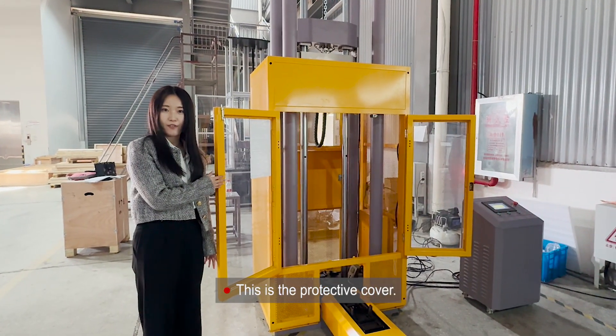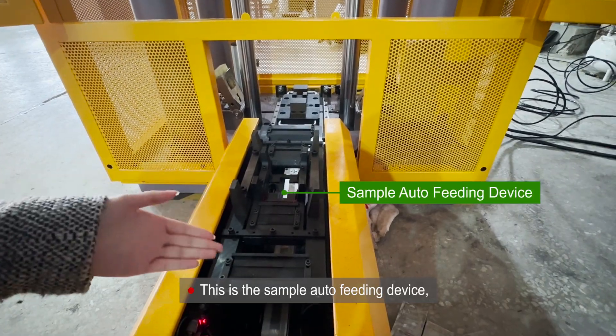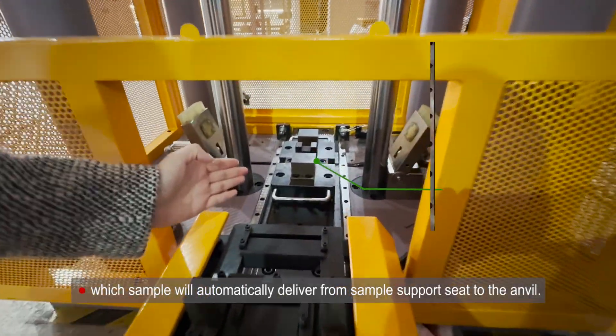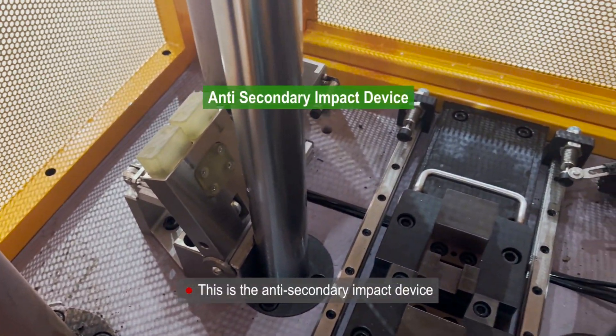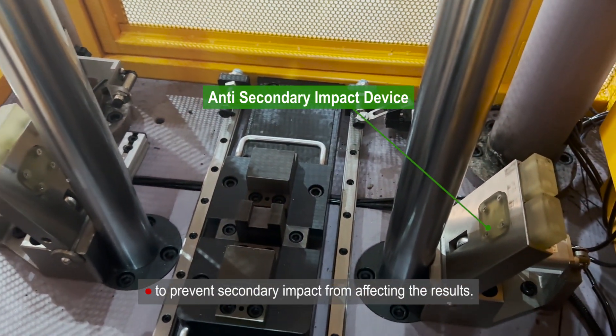This is the protective cover. This is the sample auto feeding device, which will automatically deliver the sample from the sample support seat to the anvil. This is the anti-secondary impact device to prevent secondary impact from affecting the results.